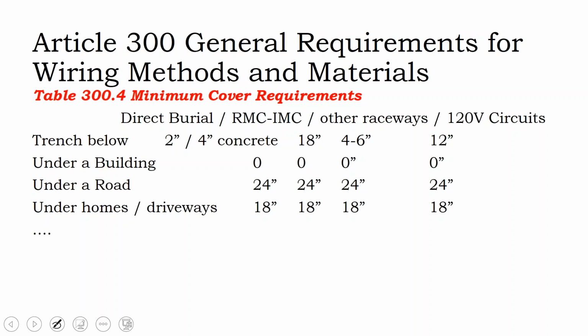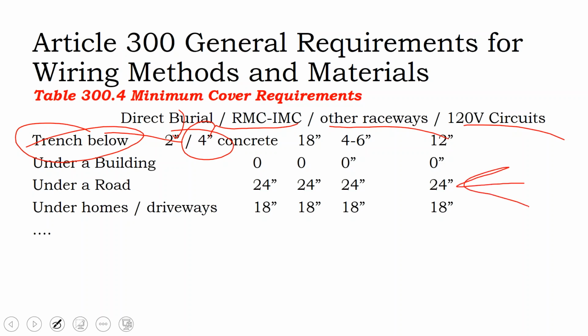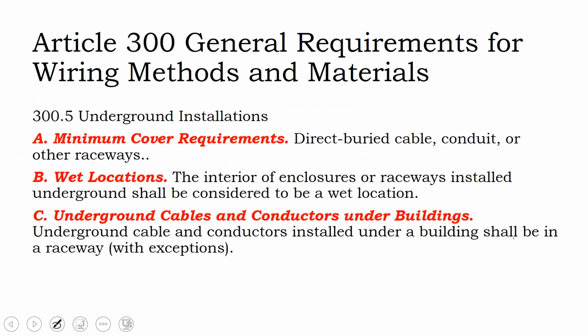There are requirements for direct burial wires, or wires that are going into rigid conduit, or using other raceways or lower voltage circuits, on the sufficient amount of depth or coverage, where if you're digging a trench and you're using direct burial wiring, I think this might have to be 2 feet deep, or 4 inches when buried in concrete. And so there's certain required depths that you have to go down to. If you want to run wires underneath a driveway, for instance, you have to have a deeper trench. If you're outdoors and you're protecting your wires and conduit, it's still considered to be a wet location.